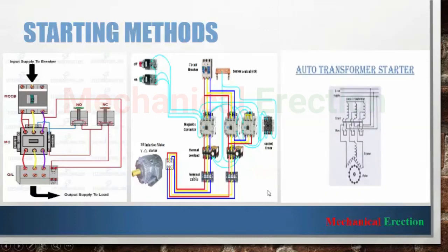The final starting method is the auto transformer starting method. In this method, an auto transformer is used to reduce the starting current. During running, the auto transformer is cut and full current is applied straight to the winding. From the diagram we can see that the auto transformer is connected while the motor is being started, and while the motor is running the auto transformer is cut from the circuit, and the full current and voltage is applied to the motor terminals from the supply.